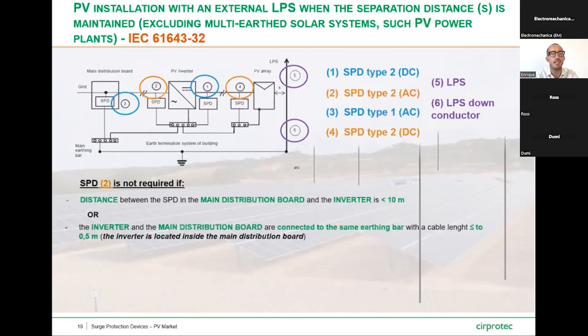Then we do have an additional SPD requirement in the location 4, close to the PV array. That should be a DC SPD type 2, and this one will not be required if the distance between the inverter and the PV array is below 10 meters.